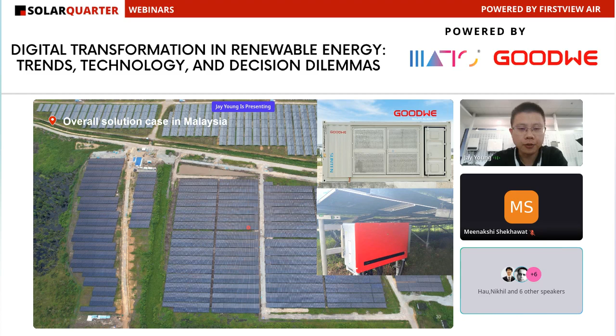This is a PV station in Malaysia, around 30 megawatts. For this station, we provided the total solution: the inverters, the MV stations, and also the station level monitoring system. We supplied everything, providing the overall solution for this station. It was commissioned in March of this year and has already been running for more than half a year, with everything fine.